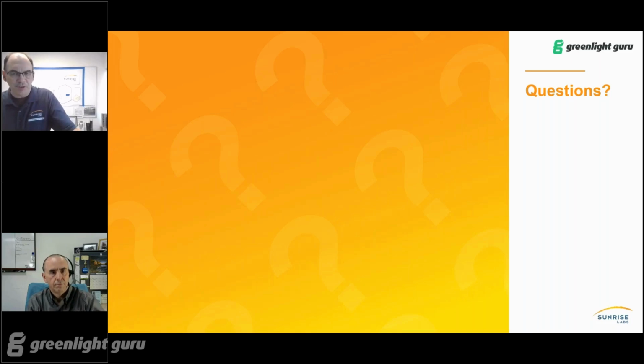So like emissions is a classic one on NRTL testing. We try and encourage pre-screening as soon as possible, so we're not getting to the final test of the project and suddenly the NRTL is saying you don't pass emissions. It happens. And also having thought through what you're going to do in that case, but getting through a pre-screen early. This can also affect things like the usability of the product, that things that may have been inadvertently missed in a formative or summative.